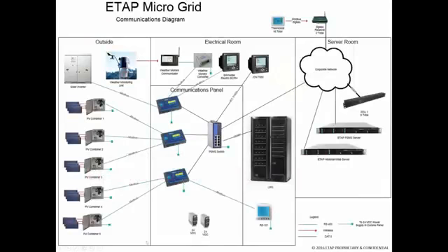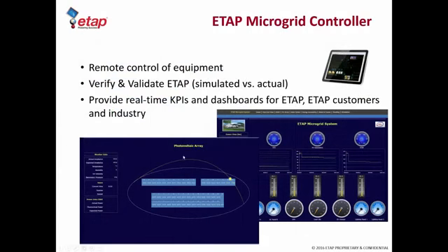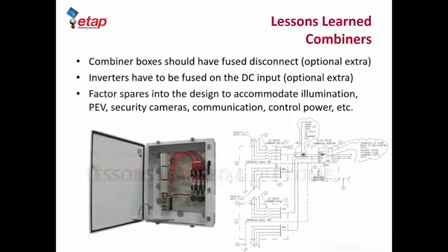And then we finally went through and connected everything together. So the solar inverter, the combiners, the weather station, the UPS, the thermostats, and the data center are all communicating into one single location that's being monitored by ETAP real-time, and it's being broadcasted into a web dashboard that we'll take a look at in a little bit. And that's a first version of that dashboard that you can see on the web or a tablet.